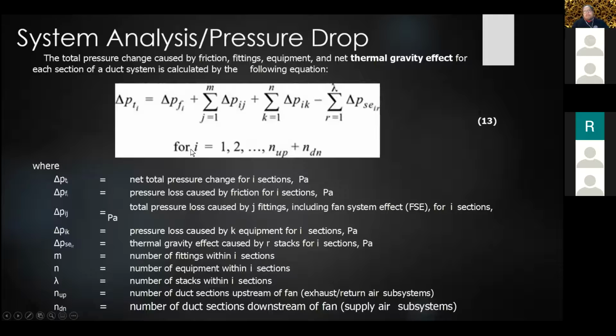So then we come to the pressure drop. The pressure drop is the total pressure caused by friction, fittings, equipment, and net thermal gravity effect for each section of a duct system, calculated by the following equation. So delta pressure, the net pressure, is equal to the pressure loss by the friction from the ducts, from the fittings, from the equipment, and from the stacks.